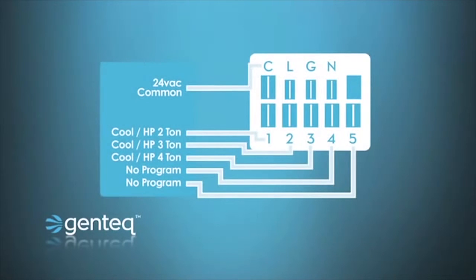Next, we see an example of an air handler application, which could be used on air conditioning or heat pump. And we again see that there are 3 taps programmed. Taps 1, 2, and 3 are programmed to work on 2-ton, 3-ton, or 4-ton systems. But taps 4 and 5 again have no program. This is very common for many X13 systems to have 1 or more taps that have no programs in them, especially when it's on such a specialty type system as a package system or an air handler.